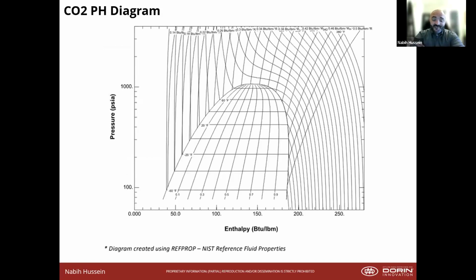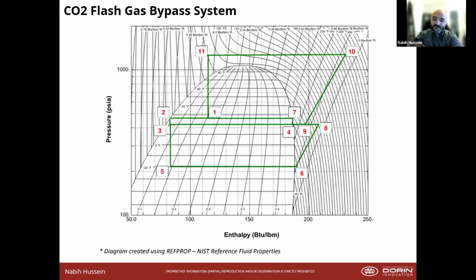This is the CO2 PH diagram, very similar to any other refrigerants you would work with. And then this is a superimposed CO2 flash gas bypass system. Number one is where you're entering that flash gas bypass tank. But what we will be focusing on is number 6 to 8, which is the low temperature compressor, and then 9 to 10, which is the medium temperature compressor, which will go into transcritical CO2.